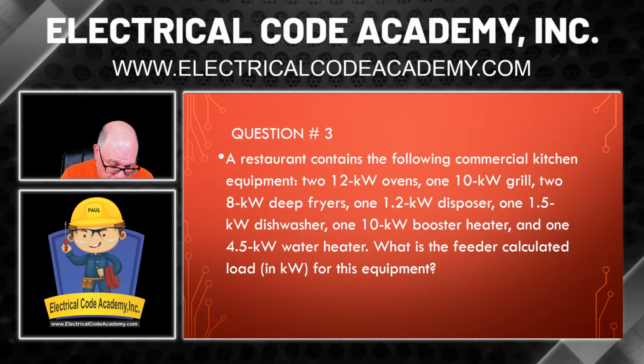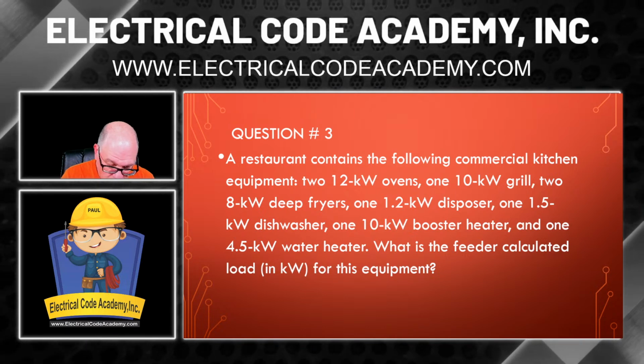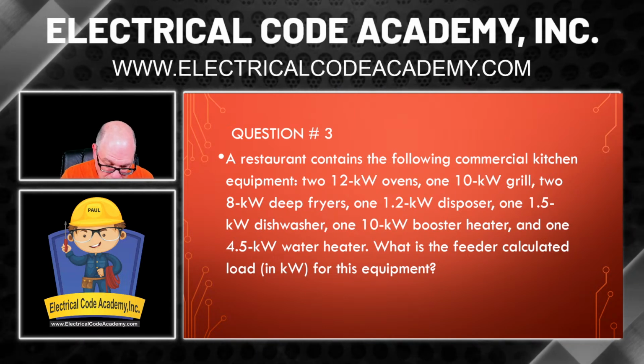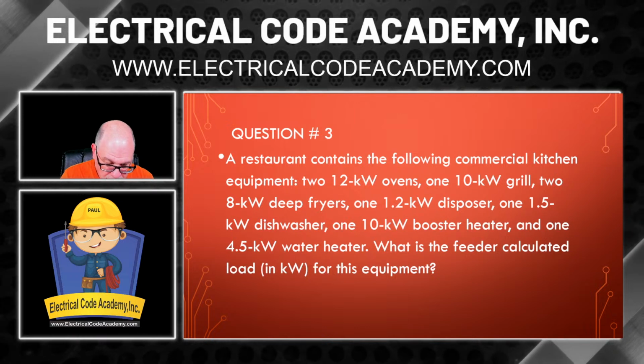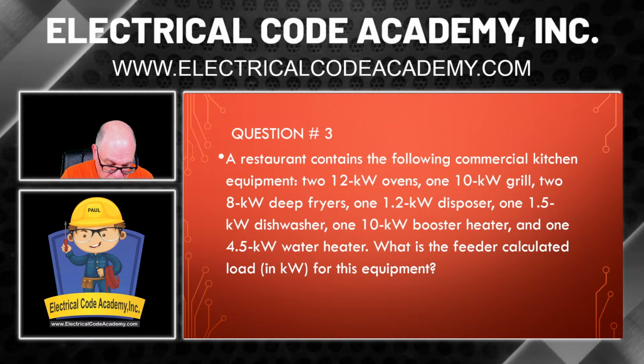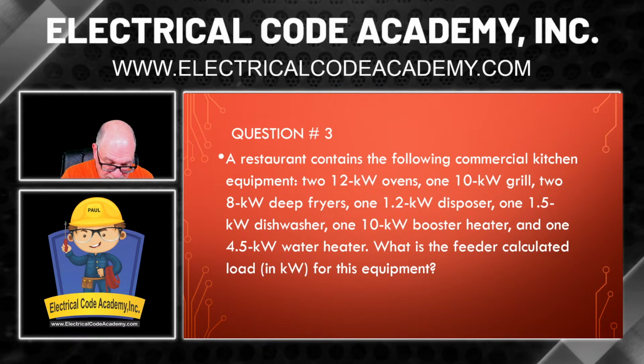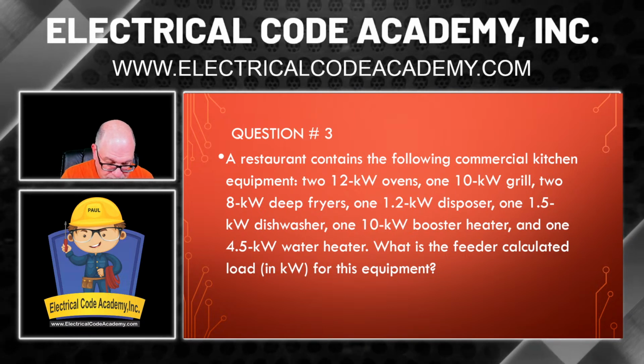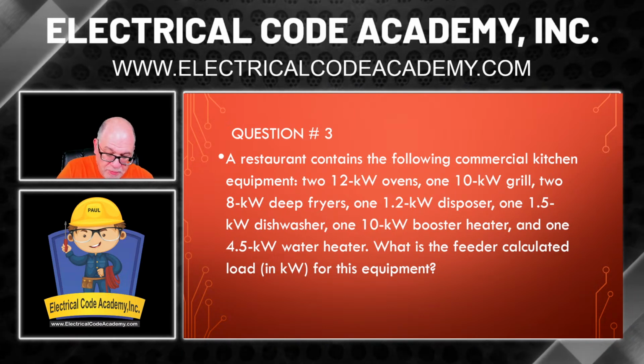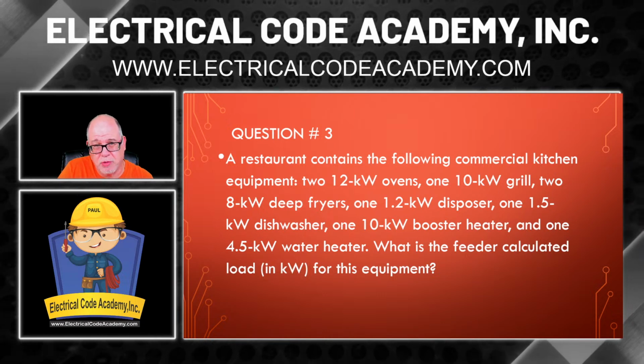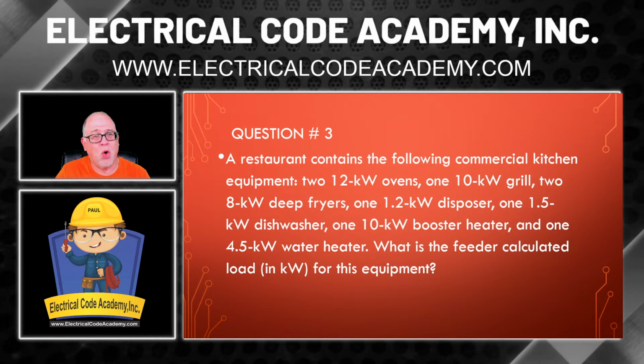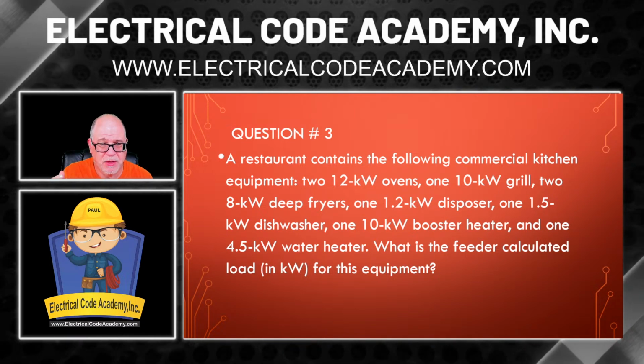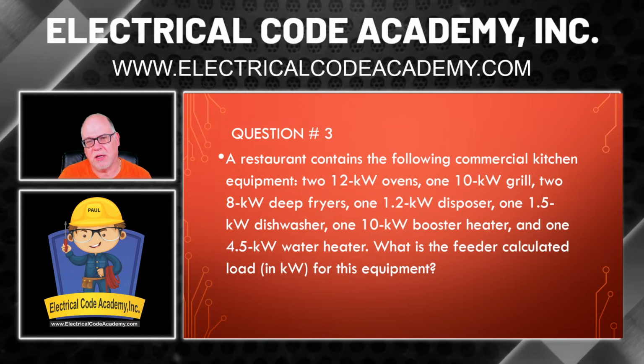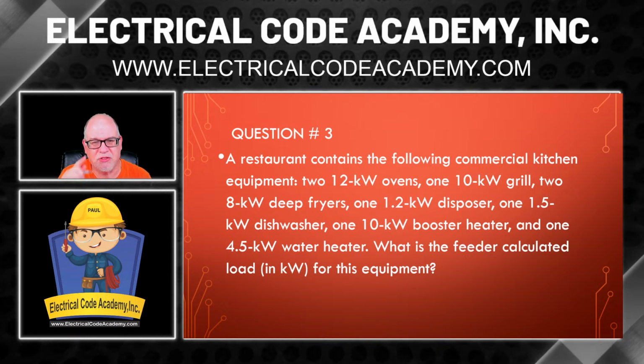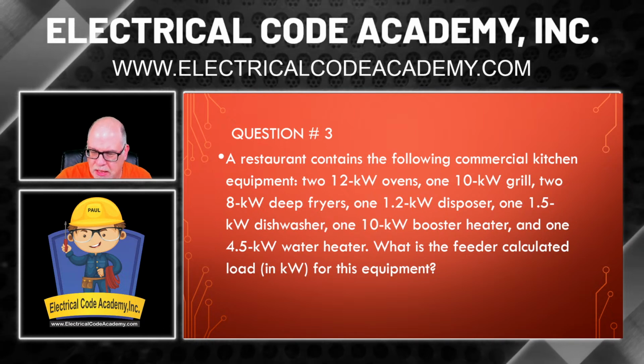So I'm going to add up 12 plus 12 plus 10 plus 8 plus 8 plus 1.2 plus 1.5 plus 10 plus 4.5. That gave me 67.2 kW, okay? So at least I know what they're all added up to be, right? Now let's see how we're going to work this in the code, okay? Because that's what we've got. So now we're going to go to the NEC, and we're going to be looking at it.